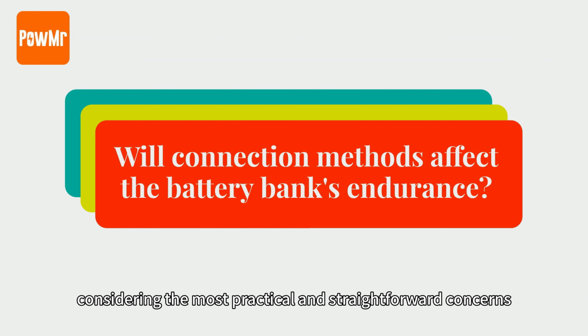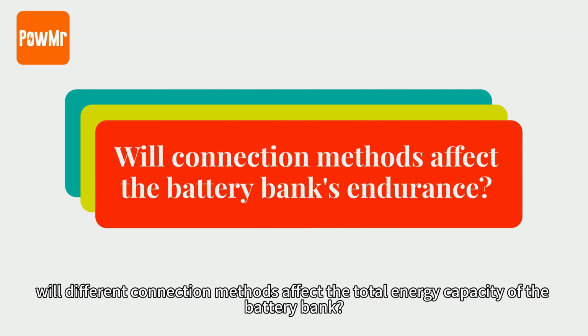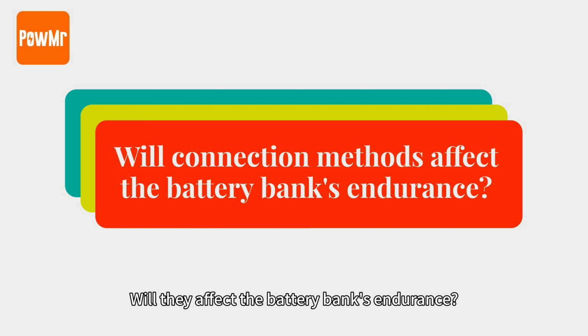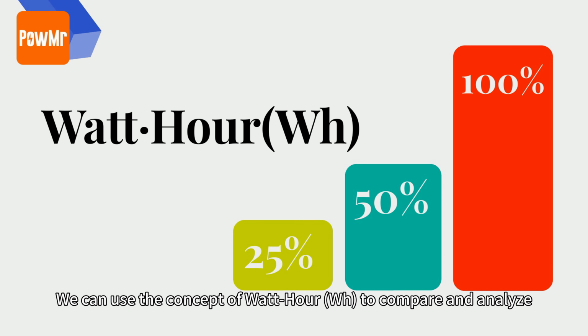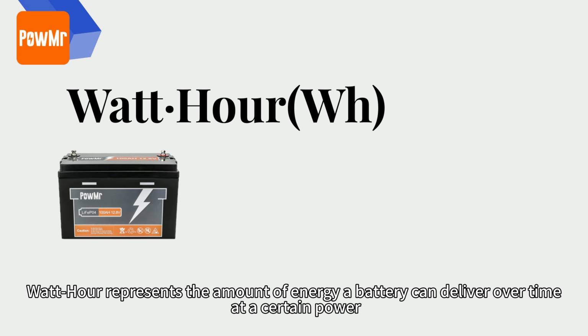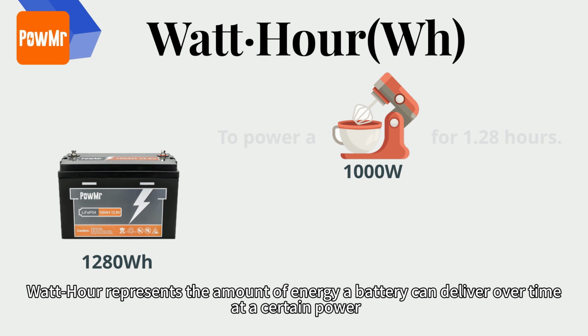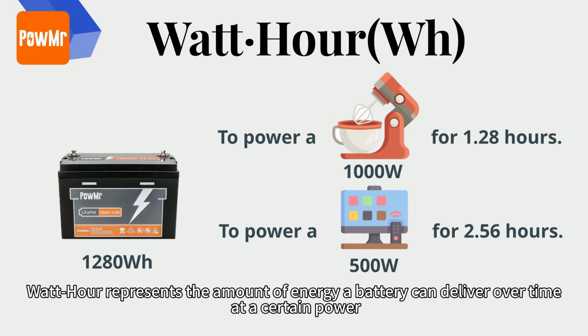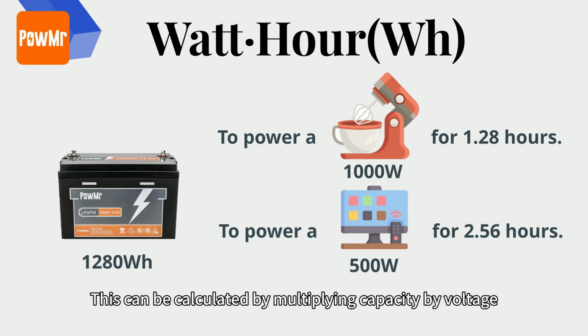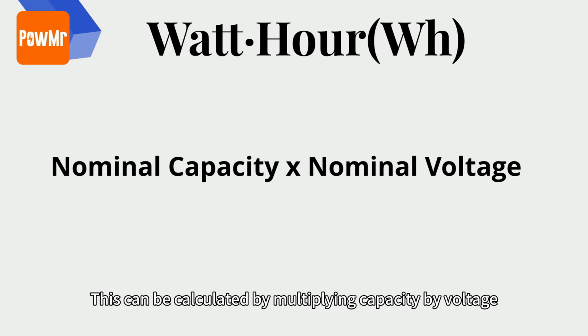Now considering the most practical and straightforward concerns, will different connection methods affect the total energy capacity of the battery bank? Will they affect the battery bank's endurance? We can use the concept of watt-hour to compare and analyze. Watt-hour represents the amount of energy a battery can deliver over time at a certain power. This can be calculated by multiplying capacity by voltage.